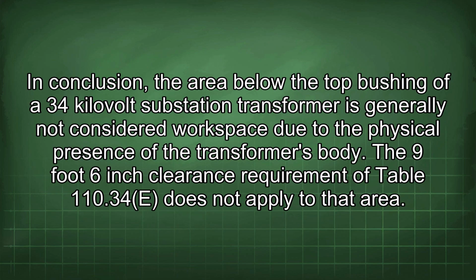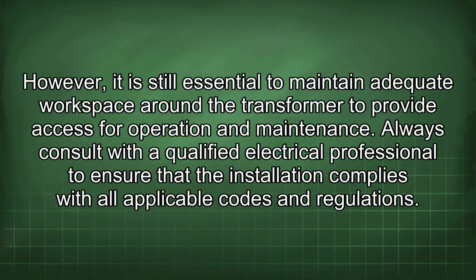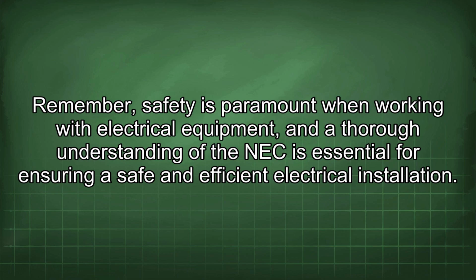In conclusion, the area below the top bushing of a 34 kV substation transformer is generally not considered workspace due to the physical presence of the transformer's body. The 9-foot 6-inch clearance requirement of Table 110.34(E) does not apply to that area. However, it is still essential to maintain adequate workspace around the transformer to provide access for operation and maintenance. Always consult with a qualified electrical professional to ensure that the installation complies with all applicable codes and regulations. Remember, safety is paramount when working with electrical equipment, and a thorough understanding of the NEC is essential for ensuring a safe and efficient electrical installation.